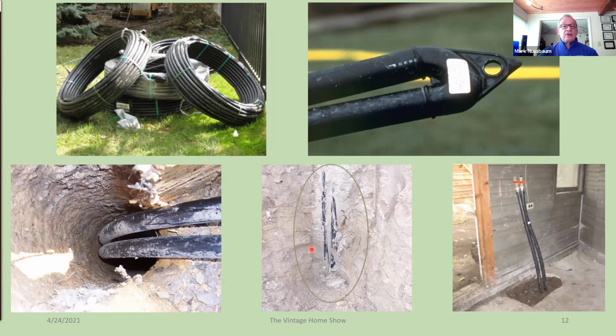And then once we've drilled that hole, we come back in and sometimes we'll connect the pipes together outside. We do that at about 4 to 5 feet below the ground, and then trench them over or directionally bore them into the building. Sometimes we'll bring them in individually. A 500-foot hole I typically will bring in individually. So I'll have a bunch of these lined up depending on how many holes you've got. For the shorter holes, sometimes we'll gang them together, maybe 3 or 4 shorter boreholes ganged together to a single set of pipes in the house.